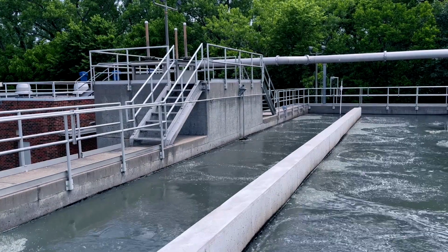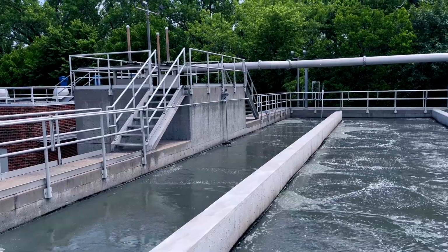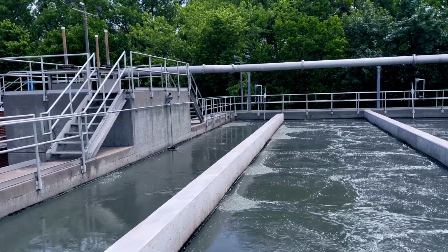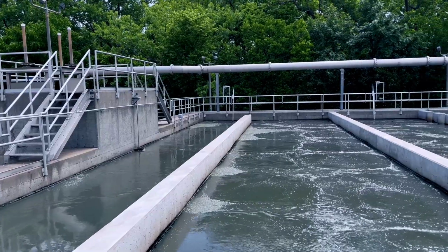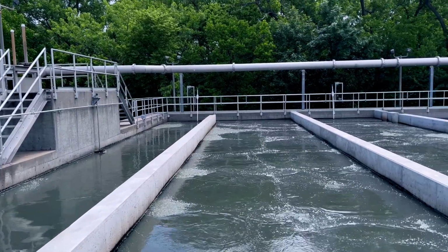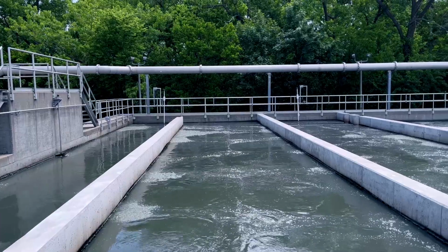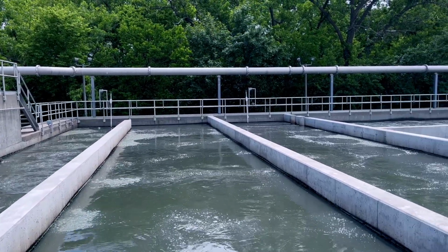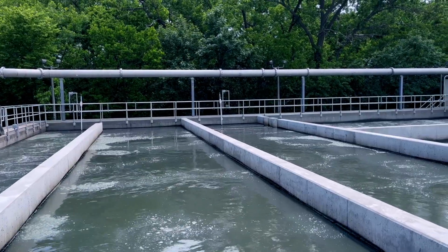Next, the wastewater falls over gates in the head cell and enters the first of the 3 channels. The first channel allows the sewage to go through an anaerobic, absence of oxygen, stage. In this channel, the pumps return special bugs to the head of the plant to keep the process seeded to treat the wastewater. Bugs are microorganisms that break down organic material in the water.